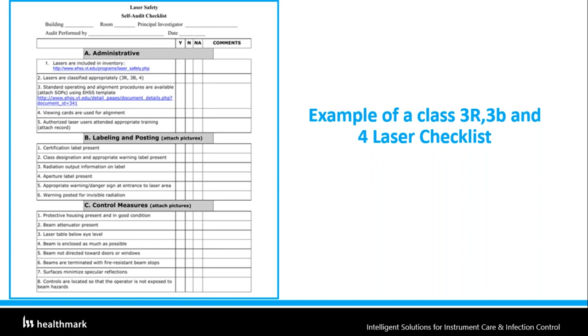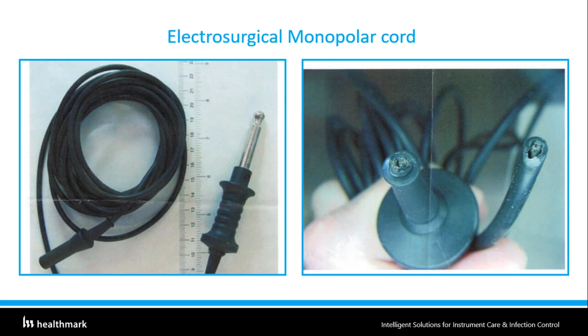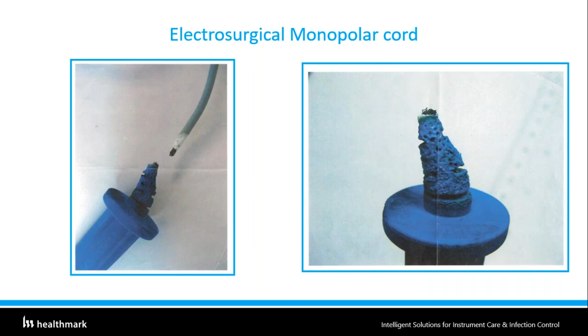But there are other items in the operating room that do not get as much attention as the laser. For example, electrosurgical monopolar and bipolar cords. There are several reports in the MAUDE database of issues they have caused. See this one on the next slide, please, where some actually caught fire in the operating room during use. In this particular report, it said that the surgeon was not getting enough power at 30 watts, so they increased from 30 to 45 watts, and all of a sudden a spark came out, and it fell to the ground and was detached from the electrosurgical unit. Next slide, please.